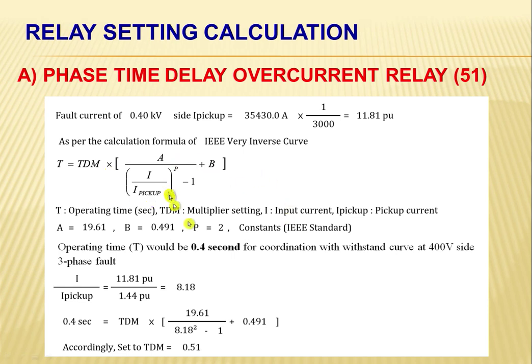Okay, so from the IEEE standard, these A, B, P constants are given already. For A, we have 19.61. For B, we have 0.491. And for P, we have 2. Okay, so our operating time will be 0.4 second as we discussed earlier for coordination with upstream relays as well. Okay, so this I over I pickup here is the ratio, and we have here 8.18.